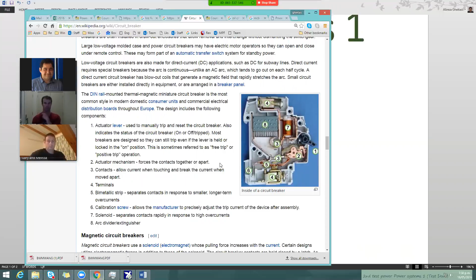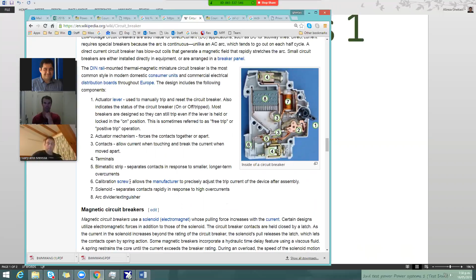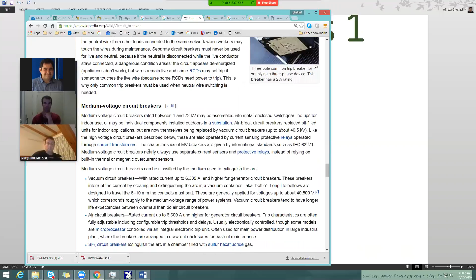So it's showing how it works. Basically all circuit breakers, including MCB circuit breakers, have one fixed contact and one movable contact, and either using magnetic or thermal means, they have a process where the movable contact moves. So the magnetic and thermal mechanisms are all here.